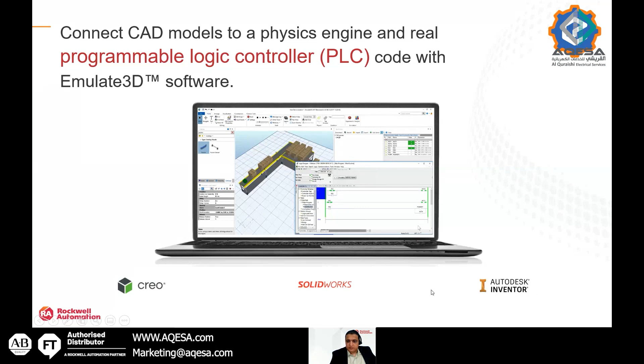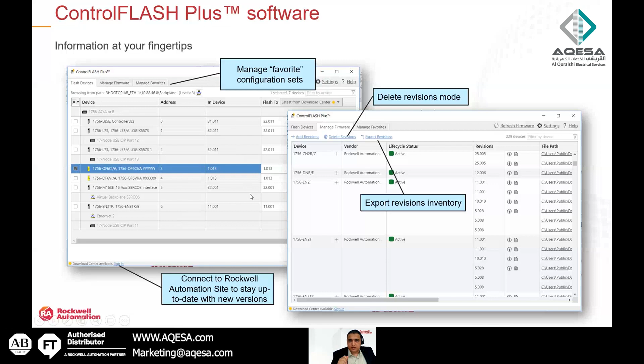Another thing about Control Flash Plus - if you know our Control Flash, this software was used to burn the firmware on new devices. When we used Control Flash before, we needed to burn one device at a time. We now have Control Flash Plus, which has been around for about 2 years, but maybe not everyone is aware of it. It's software where you can see all the devices and modules on the network, and you can burn or upgrade the firmware immediately, all of them at the same time.